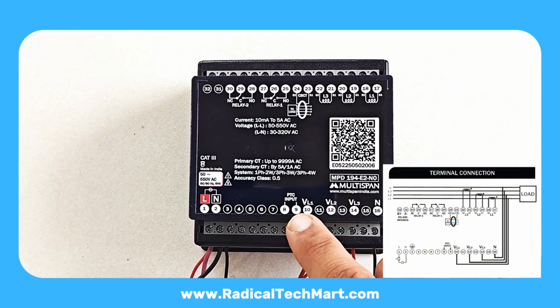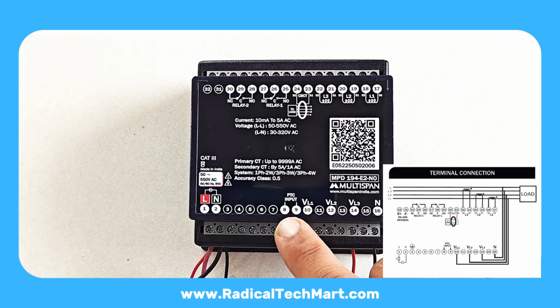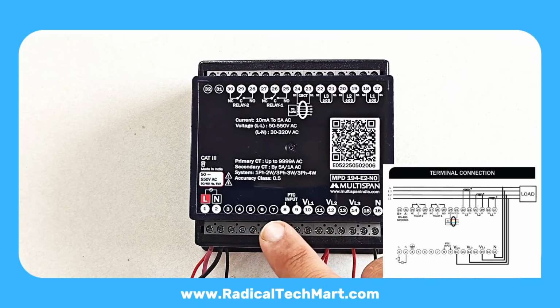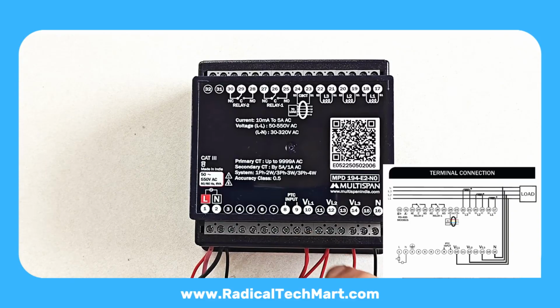Terminals 8 and 9, PTC input. Here we connect the PTC sensor that is embedded inside the motor winding. This allows the device to monitor motor temperature. When motor temperature goes high, the relay trips and protects the motor.